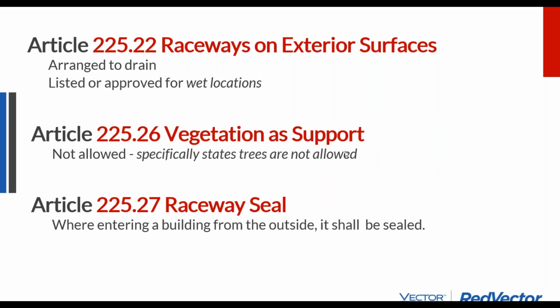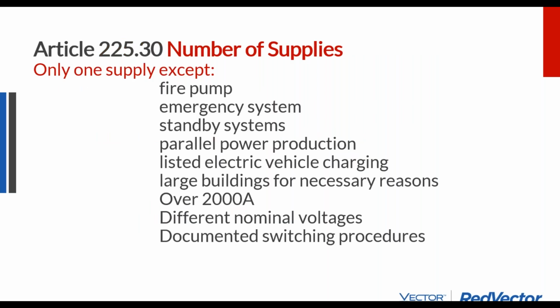Or even worse, they'll open up the box in the wintertime and it'll be full of ice. And where is this water coming from? It could come from rain sliding down the conduit into the box. It could also come from the inside of the box itself, if you're allowing airflow from the colder temperature to the hotter temperature to go through. So raceway seals are a common electrical exam question and a common oversight from an installer. Anywhere you're going from the inside to the outside, from one cold temperature to one hot temperature, the inside of that raceway needs to be sealed.